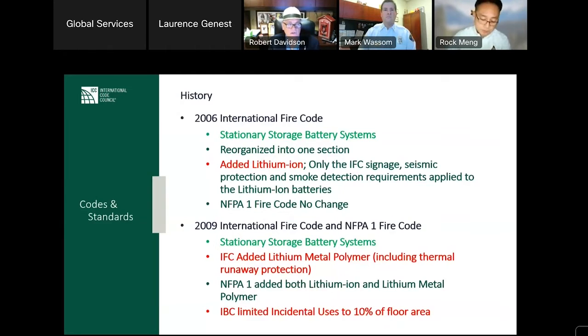So 2006 code, notice it's still stationary storage battery systems, primarily standby batteries, all right? They're waiting to be used. They're not being cycled as we do today with energy storage systems. We added lithium-ion batteries to the 2006 fire code based on the presentation, which pointed out they're low maintenance, virtually none, extremely safe, and the documentation provided to the committee claimed that they did not go into thermal runaway. We know now that that's not the case.